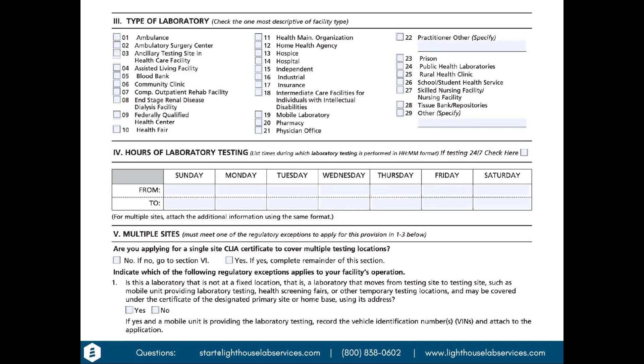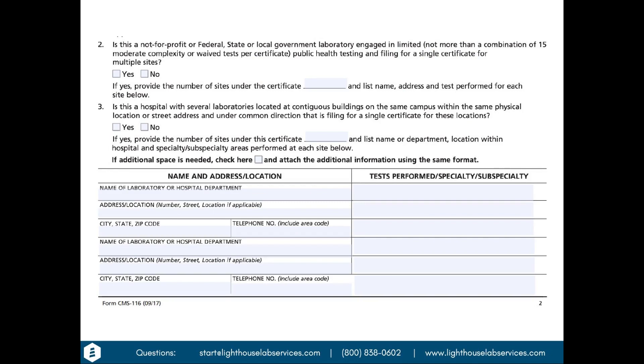Section 5 is going to almost always be a no. We've filled out this form over 50 times and there was only one instance where it wasn't a no — for a long-term care lab providing multiple CLIA-waived locations so they could spin blood before taking samples to do point-of-care testing in the field. For most labs, you're going to be a no here. If you do fall into that category, the instructions are simple: there's a list of exemptions to meet, and you'll need to list the addresses of every location where testing is performed.